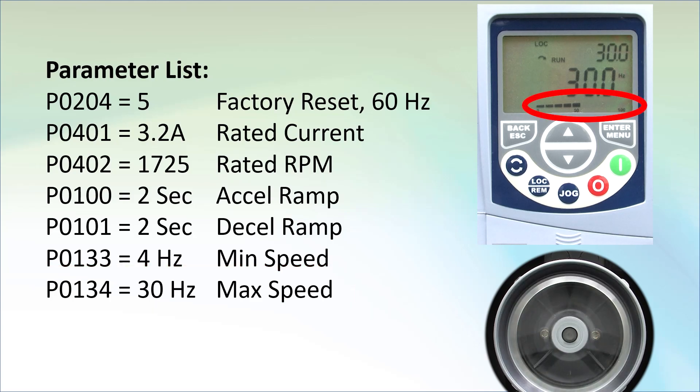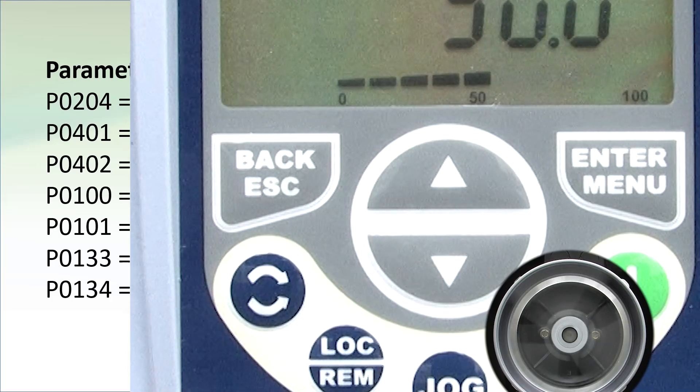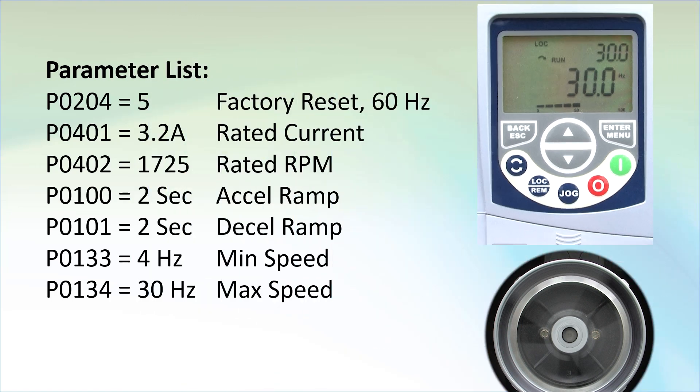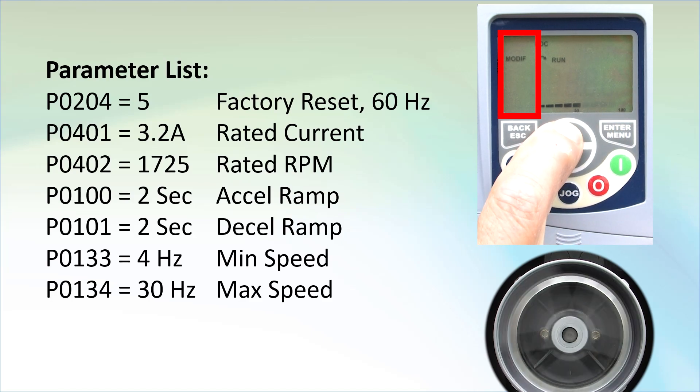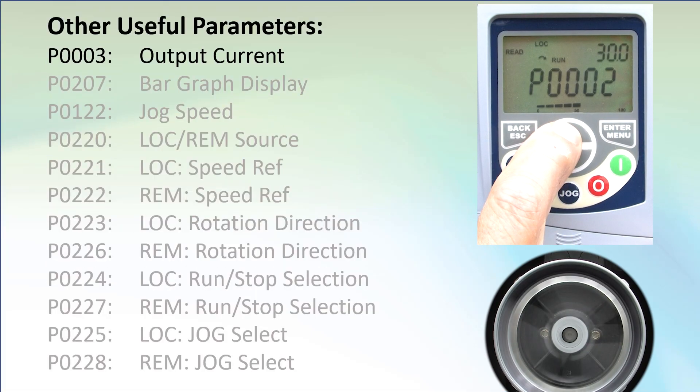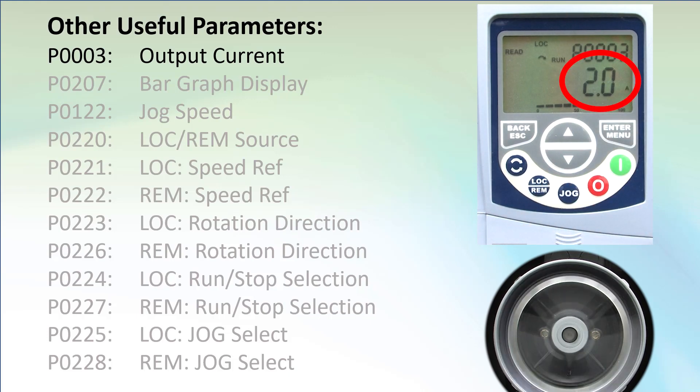The bar graph down here is showing us the percent of rated current. Looks like around 60% of rated current. Our rated current is 3.2 amps and 60% of that would be around 2 amps. If we drop into the parameter menus and arrow to the read menu, enter into that and scroll to parameter 3, we can see the actual current. Yep, about what we expected. By the way, parameter 207 controls what the bar graph displays.